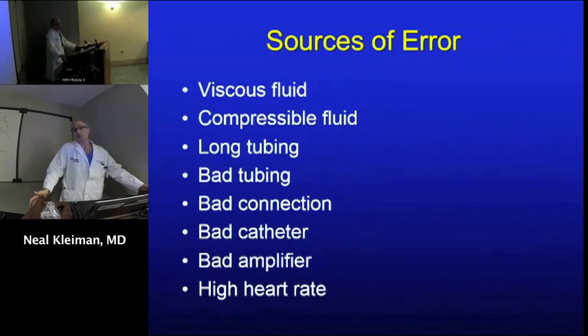Bad connection, goes without saying. Bad catheter—what's a bad catheter? Narrow catheters transmit pressure poorly. Why? Because relative to the amount of blood or fluid that's in there, there's a relatively large surface area around the perimeter. So what do you get? Friction. So it generates heat.